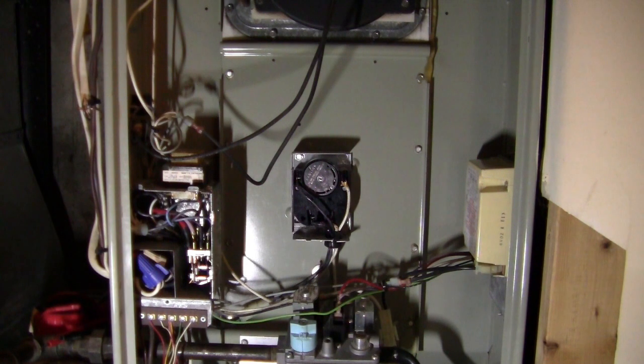Or the worst scenario, because this thing actually works as it's supposed to, like your fan or your filter or whatever, the ductwork has a problem, and you need to fix that before you reset this thing. If you just keep resetting it, you're going to have overheating inside your chamber, and you're going to have poison air come into your living area. That is not what we want.